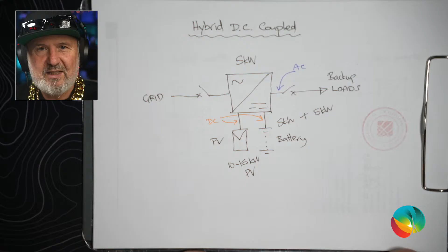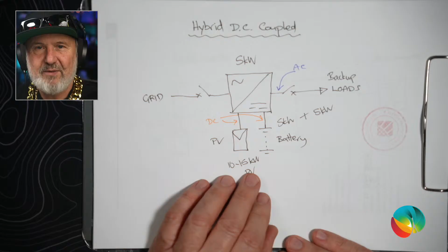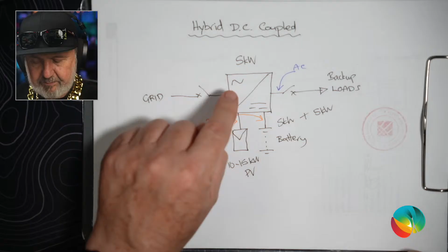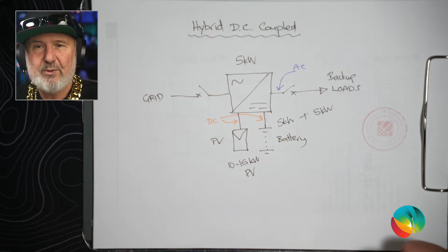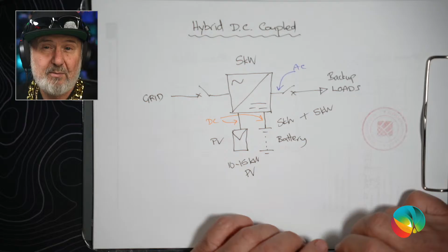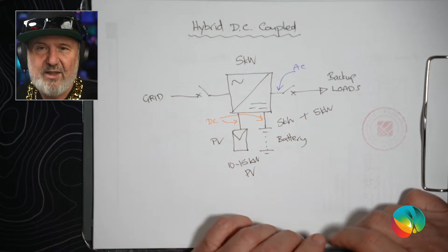This might come as a shock to you, but not every day is a perfect sunny day all day long. So your 15 kilowatts of solar on a day like today, which here in Mount Tillibawong is grey and overcast, is probably only putting out 2 kilowatts. So having all that extra PV power isn't a problem. It's actually an advantage for getting more renewable energy more of the time into your system, into your loads and into your battery. And the limitations on this are that the power conversion at the inverter will often have some current limits. What they'll say is their maximum input current, IMP, and also their maximum short circuit current. Now those limits have to be considered.